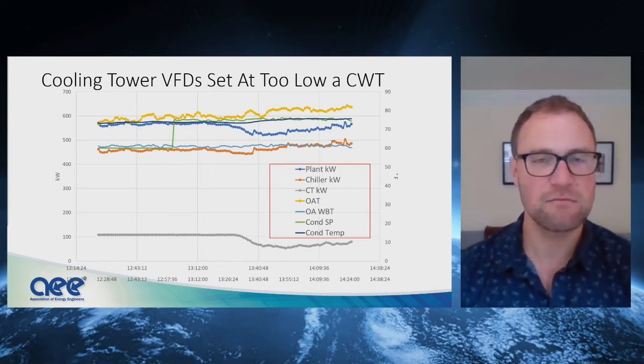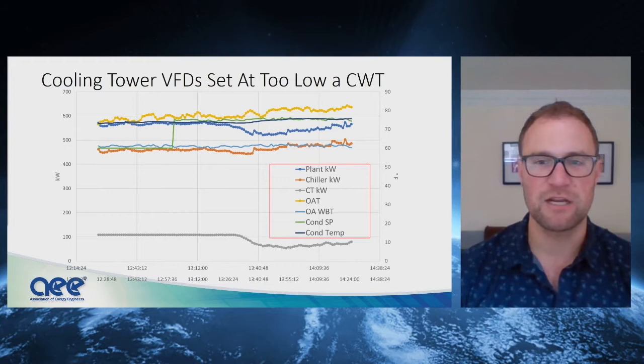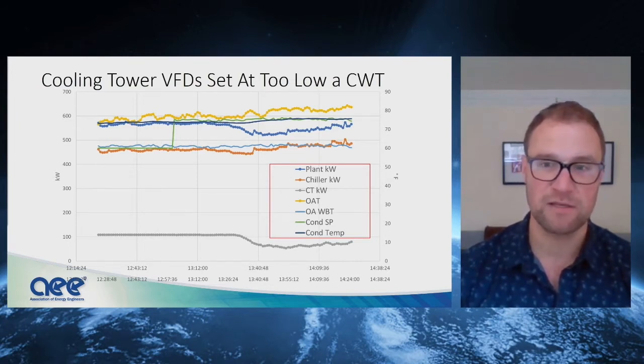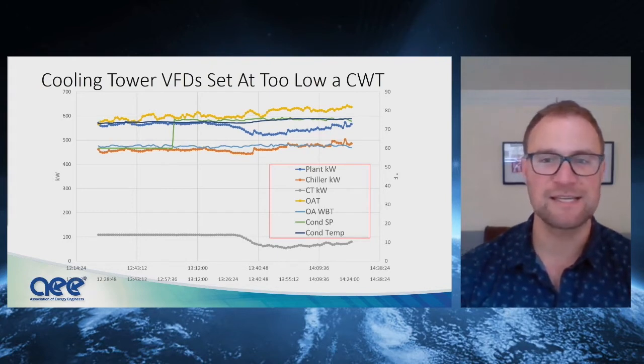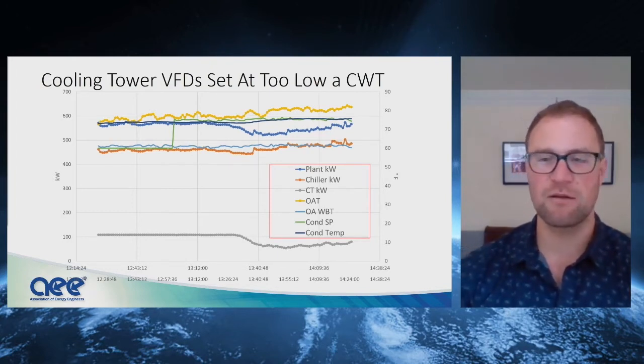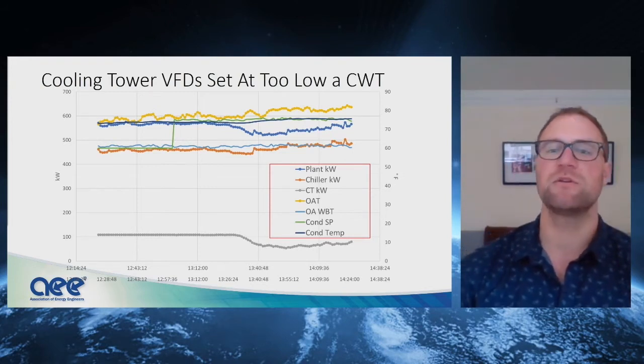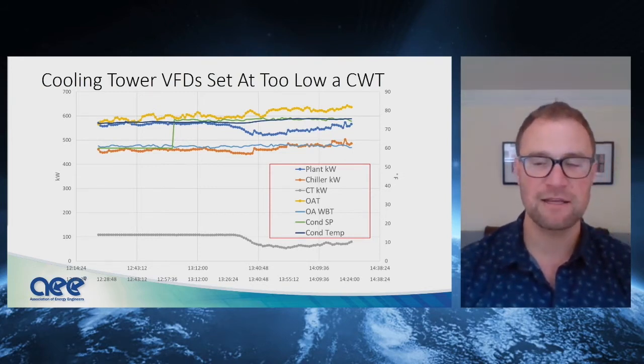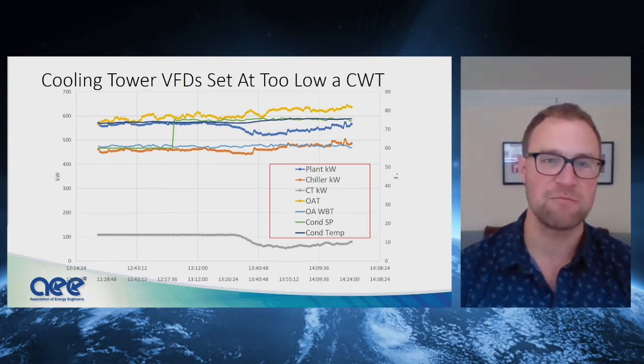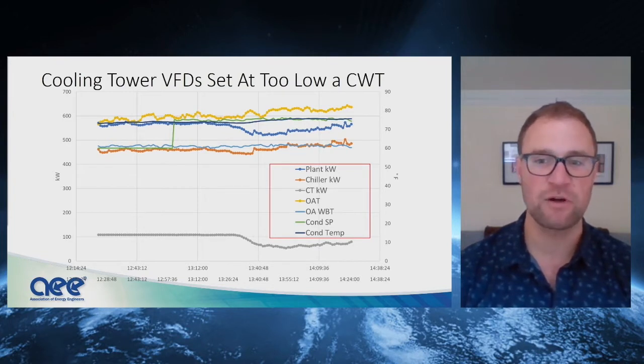So as you can see in this mess of spaghetti noodles on the screen, the green line is the condenser water temperature set point. It was initially set somewhere around 60 degrees. So the customers thought, well, it's nice and low, we're nailing it, no opportunity. But in reality, that condenser water temp set point was set to a temperature that the cooling tower fans just weren't able to achieve. So you can see the actual condenser water temp trend line in black. In this case, it kind of hovers between 74 and 76. It never drops below that.